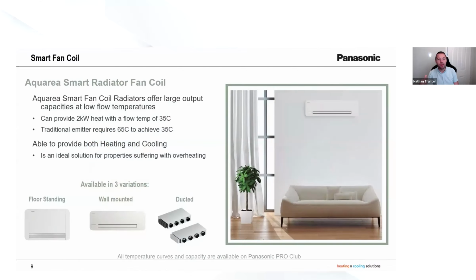We also have a few different ranges of smart fan coils. The good thing about fan coils is that on a heat pump, if we can, we want to run at a lower flow temperature, and this is where fan coils come into their own. For example, I could have a 35-degree flow going around one of the fan coils you can see on screen right now, and that will provide an output equivalent to a 65-degree flow in a standard radiator.